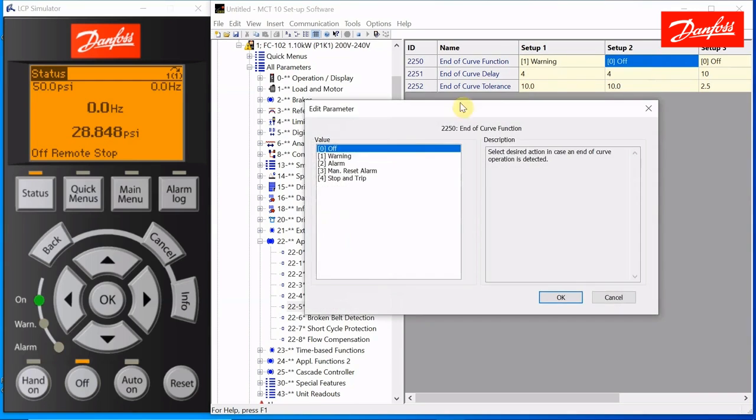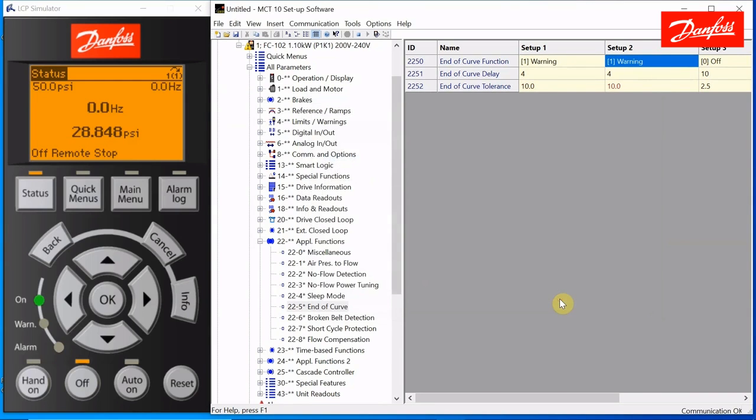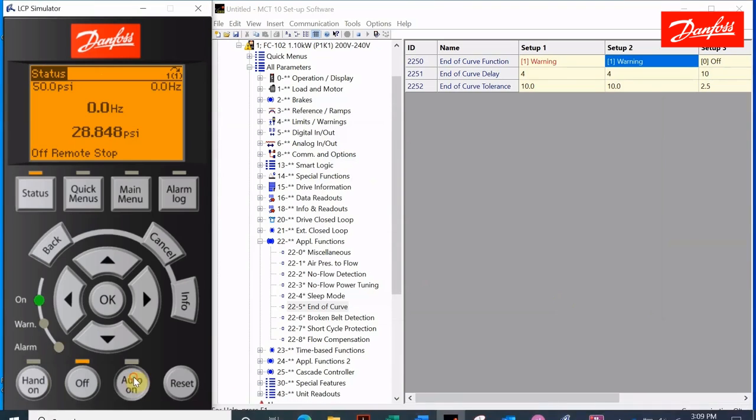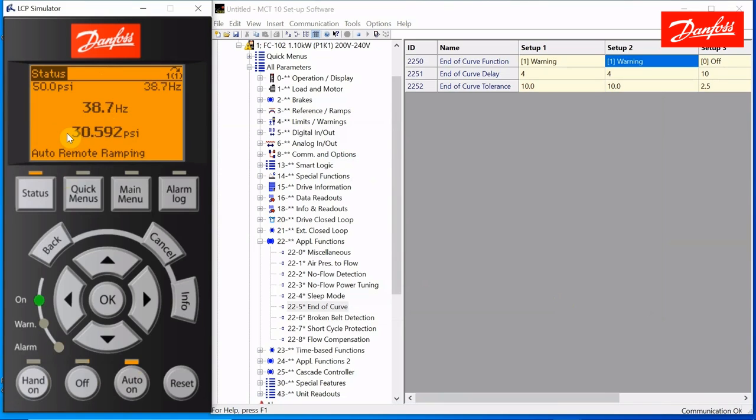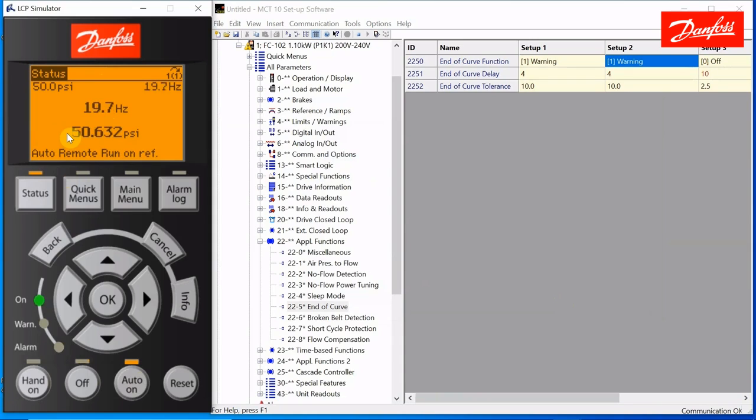We'll program this for warning. So the drive would continue running. It'll show the end of curve warning, and we'll see that it'll activate the relay. So the drive's taking off and ramping up to speed. The pressure is low. It's trying to build pressure up to set point. I'll simulate that pressure rising up to set point. And once I get there, it should steady out in speed because it figures that's the speed I need to go to make my 50 psi.